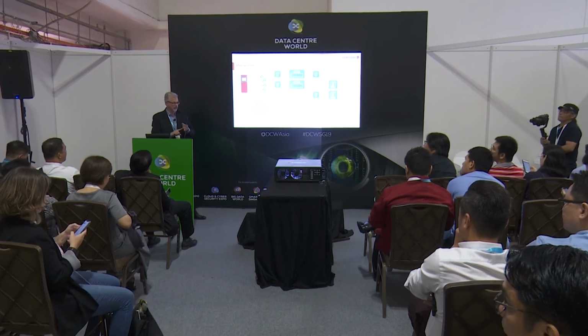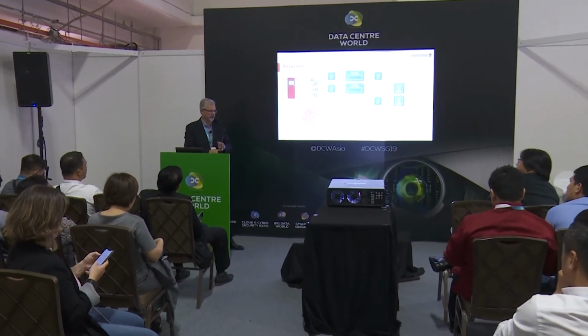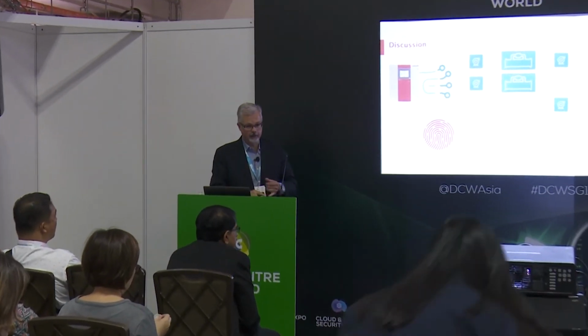So the question is, how do we account for redundancy? First, if there's a failure of equipment, we're able to predict it — catastrophic failures that occur internally to the plant are detectable. If they're caused by external events, like an airplane taking out the cooling towers, that's not predictable. So our first defensive measure is predictability, and the second is calculating the capacity that's available. If we do lose a cooling tower, we can shift the effort to the pumps and chillers instead of relying on one of three or five cooling towers, and tell the operator whether we have enough capacity for the load. The plant will continue to learn, adapt, and optimize — first to meet capacity requirements, and second for energy efficiency.